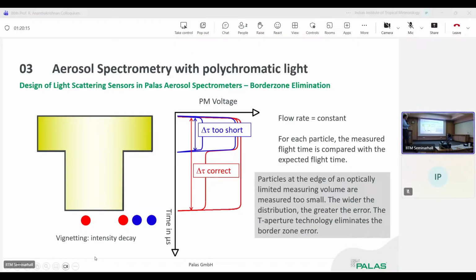At the edge of an optically limited measuring volume, particles are measured too small. This is in the outer area here. And the wider the distribution, the greater the error. It means if I measure more area, if this aperture gets bigger, of course, I have much more decay at the outer side. And this I can see by the signal height and also by the time of flight, and I can diagnose the region of flying here at the end. That's very important for us because we do high resolution particle sizing, typically with aerosols like salt or DEHS or KCl, whatever. And in order to really be exact and correct, especially for filter measurement, for the efficiencies, we need to know what we measure and what the size of the particles is, and whether this is the correct size of the particle.